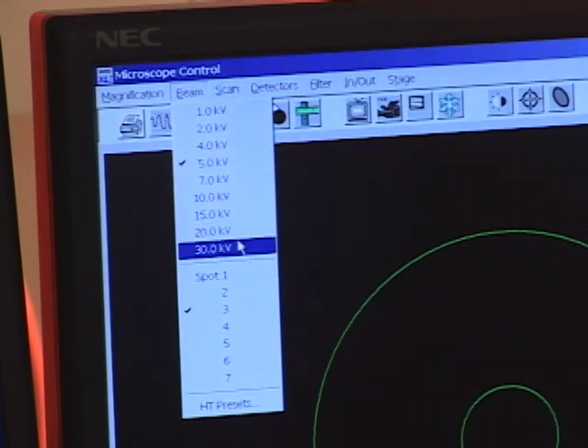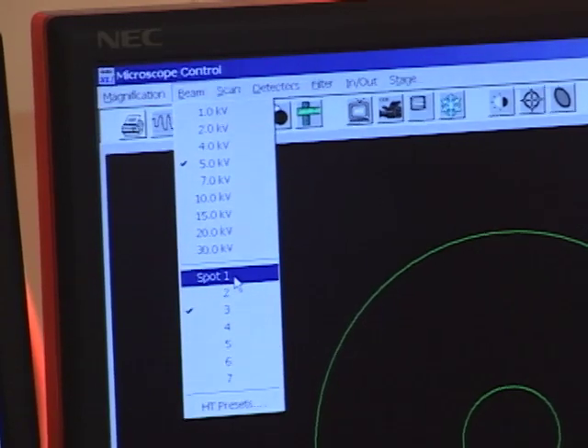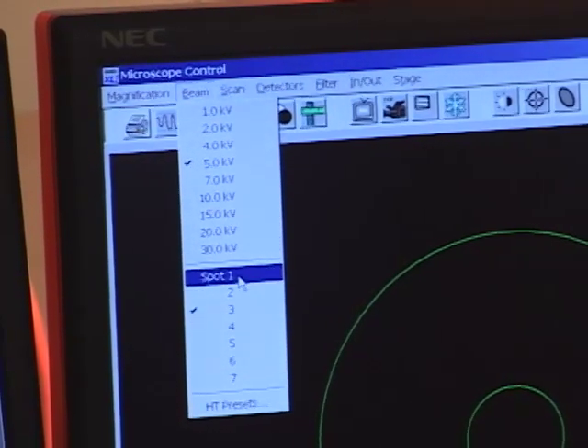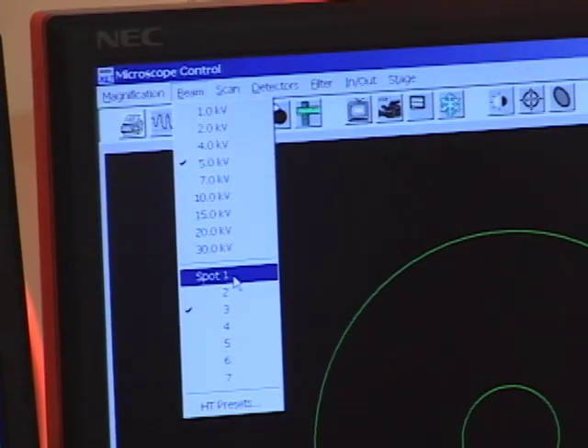Spot size then ranges from one to seven. One being the smallest diameter of electron beam and seven being the largest. Spot size one also has the least current, and so it's again less damaging and it's also the highest resolution. But because it has less current, it also has more noise. So it's a higher or lower signal to noise ratio.